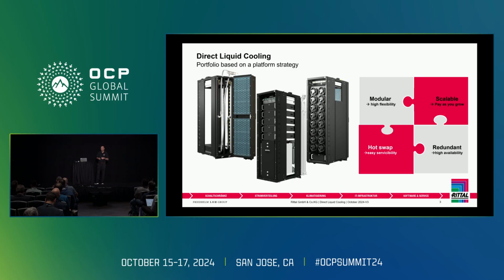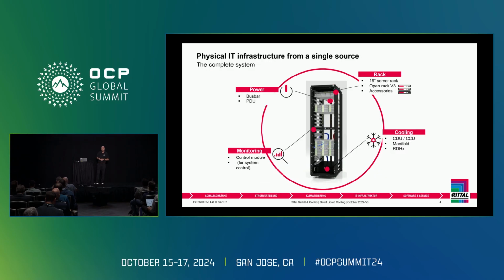I'll go through some of that detail. We're looking at this from a complete solution point of view: the rack, 19-inch or, given this is the OCP show, the 21-inch ORV3 product. Cooling with CDUs, CCUs, manifolds, rear door heat exchangers, and sidecar type units. Monitoring through control modules, and last but not least, the power, whether it's battery backup or PSUs and bus bars, rating from 20 kilowatts all the way to multiple hundreds of kilowatts as we go into next year.